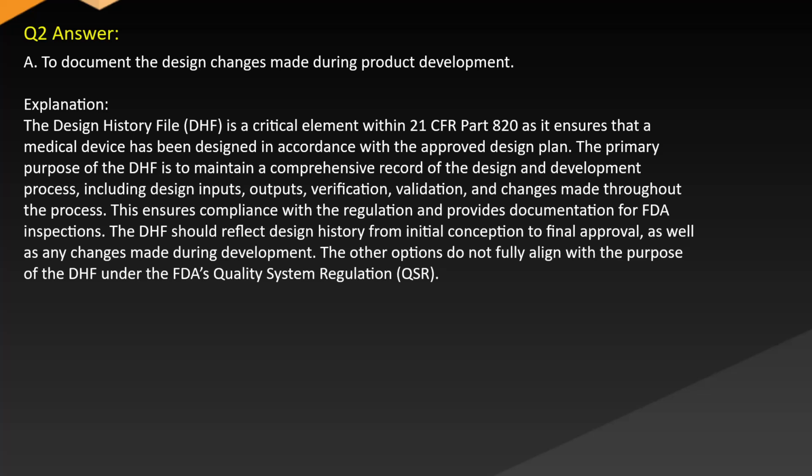This ensures compliance with the regulation and provides documentation for FDA inspections. The DHF should reflect design history from initial conception to final approval, as well as any changes made during development. The other options do not fully align with the purpose of the DHF under the FDA's Quality System Regulation (QSR).